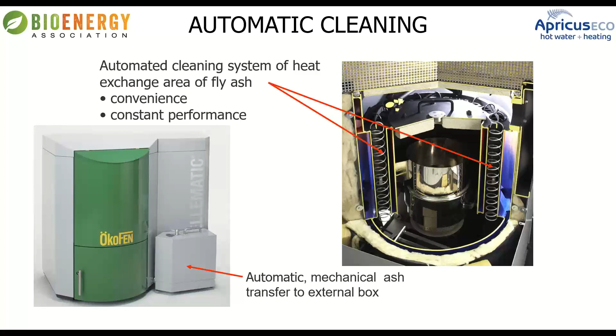So if we look at a Cascade, this is a 256 Cascade, and so we've got a pair of 128s, and they're pretty small space. We'll do some stuff on space in a minute. And in the OkoFen example, and many of the boilers are similar to this, you have Cascades. So single boilers will go up to 256 kilowatts, and then the pairs will go up to 0.5 megawatt, and then you can have multiples. And so it's really suitable for retrofit buildings because it's really flexible in where they can be placed, and they can be maneuvered much more easily in and out of doors and upstairs plant rooms and service lifts and whatever other things that people want to throw in the path to try and make decarbonisation hard. But that really does make it a lot easier. These boilers will fit through any standard 800mm door.